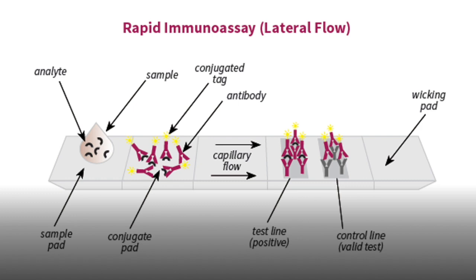The buffer continues to flow, and any unattached antibodies — those not bound to antigen — will attach to another set of secondary antibodies specific for antibodies rather than our antigen. This is the control line, and it tells us that our test is working. Finally, all remaining flow is trapped by the wicking pad at the end.